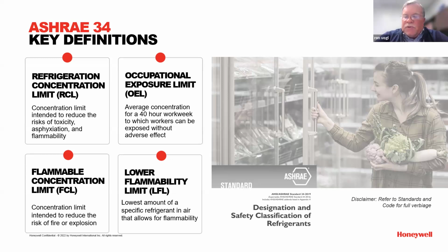Some are developing apps for the calculations. What you want to make sure is that you do not use a refrigerant or system that has the ability to put more than is allowed into a space if it leaks. It has to do with the size of the space, say an air conditioning unit, or in a refrigeration system, a walk-in cooler. LFL will be important, and all refrigerants will have their own.